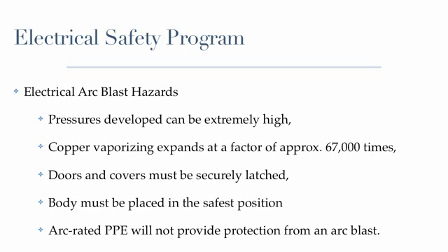From the arc blast hazard, pressures developed can be extremely high. Copper vaporizing expands at a factor of approximately 67,000 times, or the equivalent to a stick of dynamite. Doors and covers on electrical equipment must be securely latched. Our body must be placed in the safest possible position, and we must remember that arc-rated personal protective equipment will not provide protection from an arc blast.